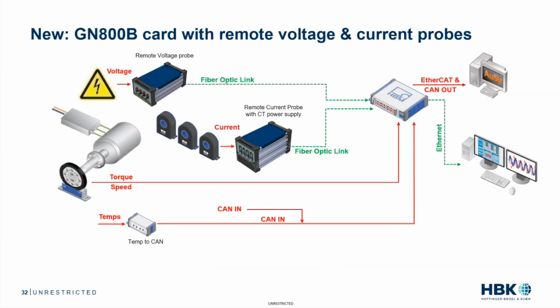Well, introducing a very unique and ultimate method for mitigating, if not conquering, EMI issues. What we have here is what we call remote voltage probes and remote current probes. Even the remote current probe in this case has an optional CT power supply built in. So ideally, you've got very short cables from the measurement point to the remote probe. And the voltage remote probe, let's say, is capturing the DC voltage from the battery and also the 3 phases of voltage from the inverter.